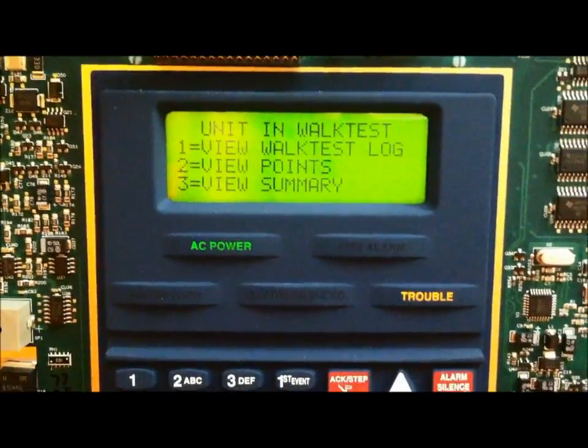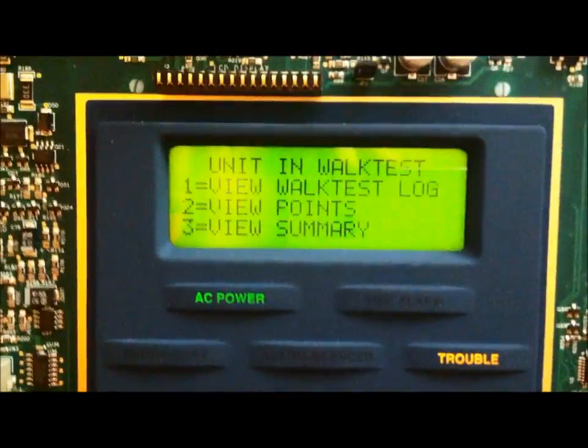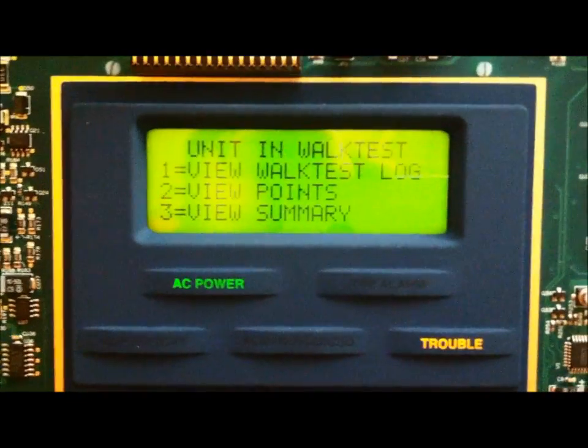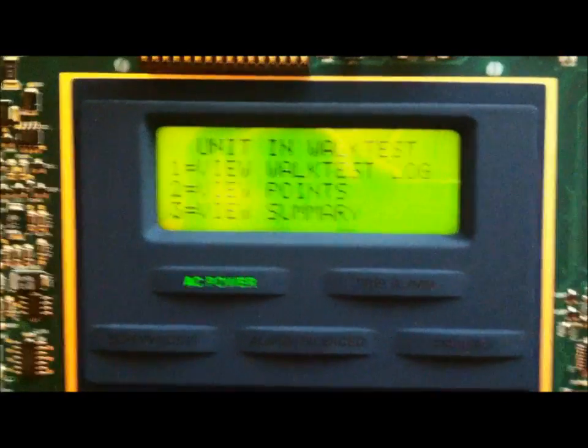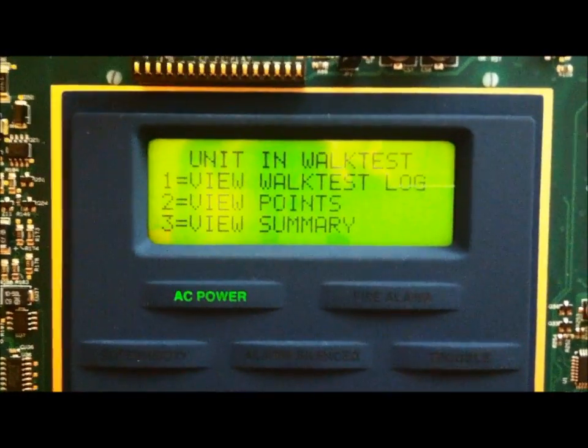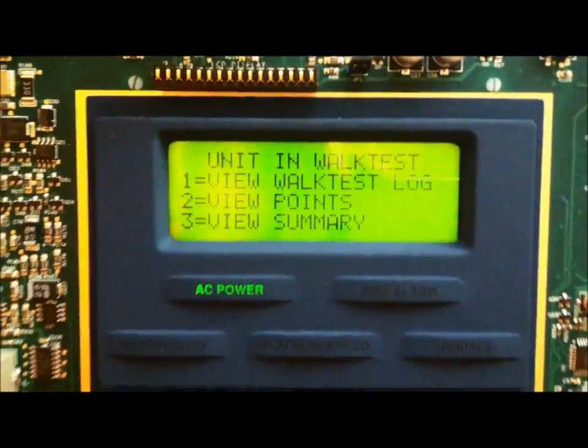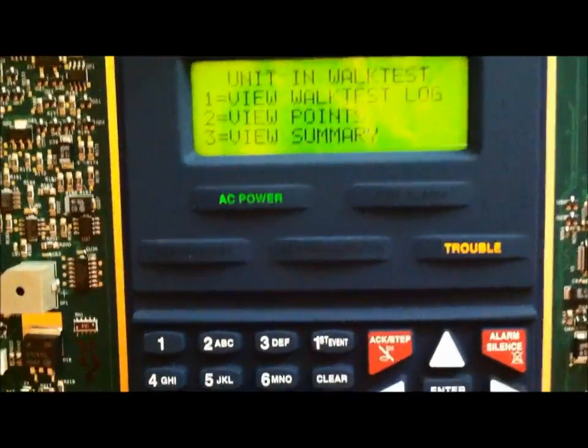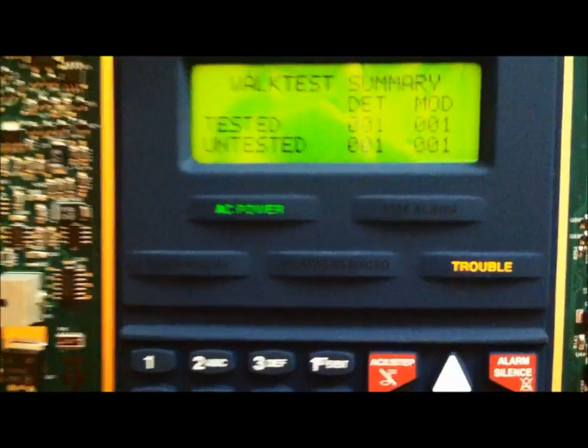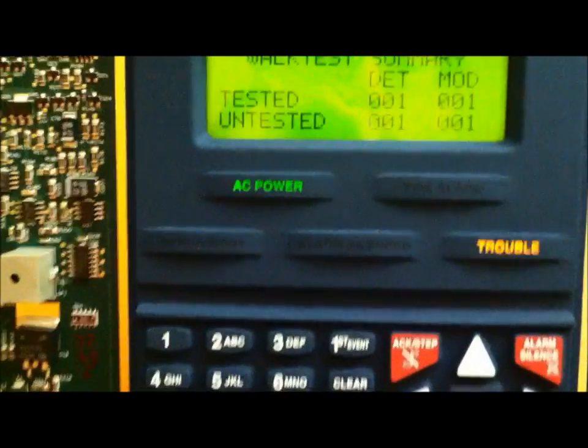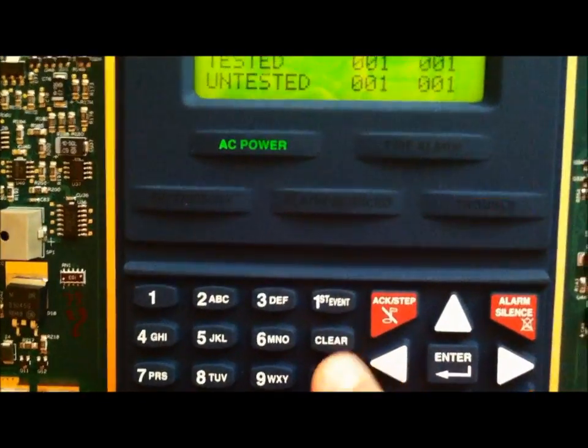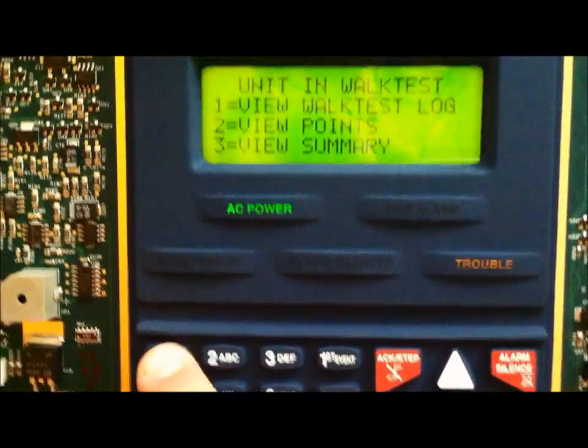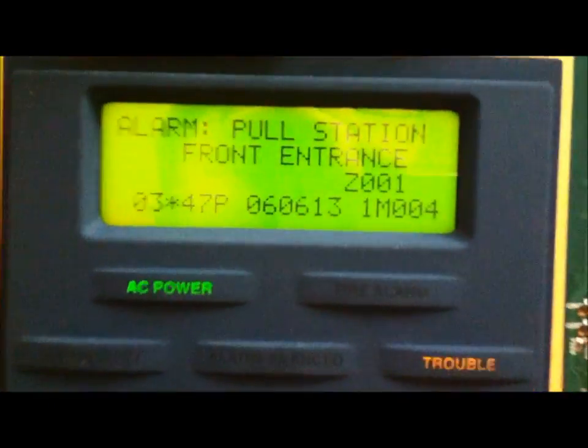Alright, so I've tested the smoke detector and click the screen if you want to see the video of me testing it. I tested it using smoke detector spray. Let's go ahead and view the summary. You can see now how one of the untested smoke detectors is now listed as tested. If we go to View Walk Test Log, it should be the one by the front entrance. That's the pull station.